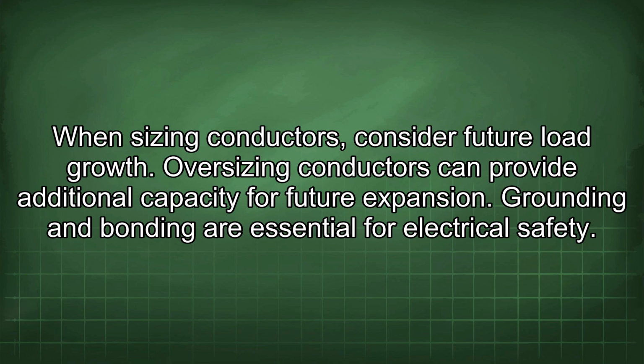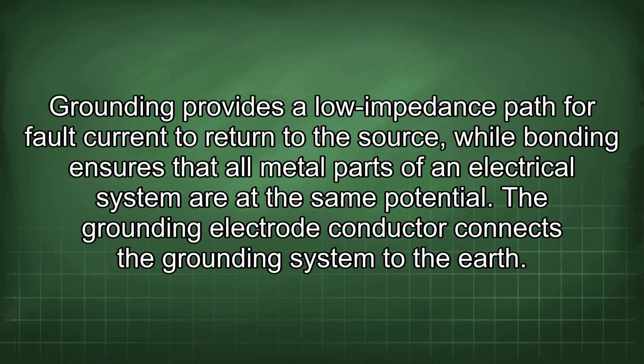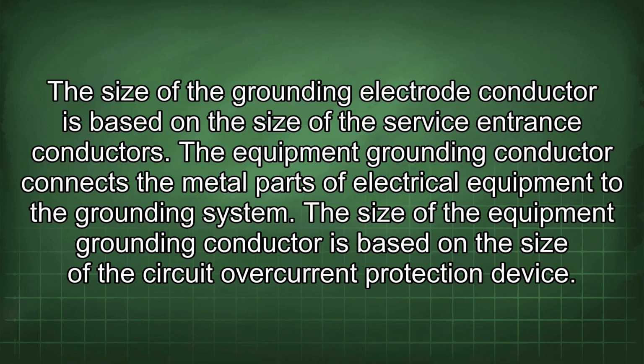Grounding and bonding are essential for electrical safety. Grounding provides a low impedance path for fault current to return to the source, while bonding ensures that all metal parts of an electrical system are at the same potential. The grounding electrode conductor connects the grounding system to the earth. The size of the grounding electrode conductor is based on the size of the service entrance conductors. The equipment grounding conductor connects the metal parts of electrical equipment to the grounding system. The size of the equipment grounding conductor is based on the size of the circuit overcurrent protection device.